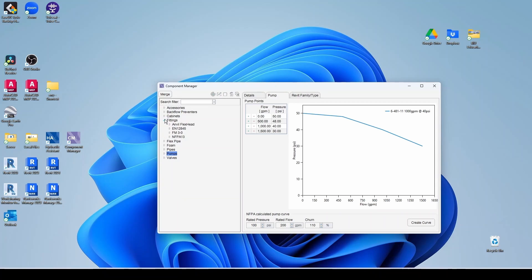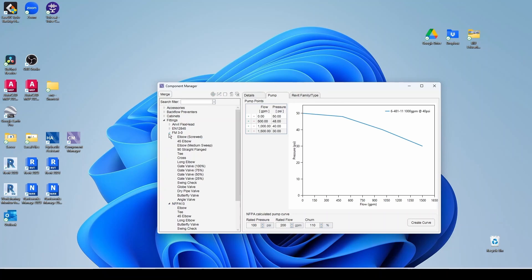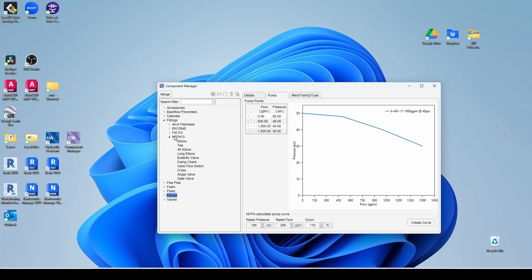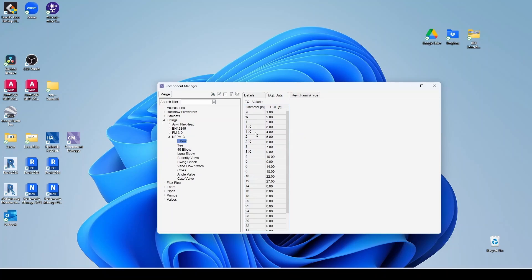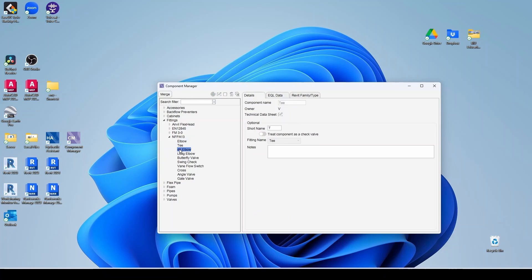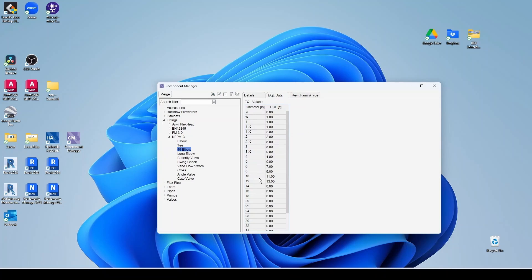Let's take a quick look at fittings here. So fittings, you have the NFPA 13 typical values. You also have FM 3-0 in case you're doing Factory Mutual projects. But in most cases, you would have like NFPA 13. So here you have your elbow. And then here's your list of equivalent length for pressure drop in feet. So you have elbow, tees, 45 degree elbow. And for each one of them, you have this table.